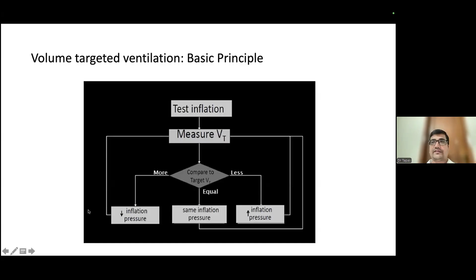Volume targeted ventilation includes many different types. The most common type is volume guarantee, which is present in the majority of ventilators like the Draeger Babylog 8000 Plus and VN500 Accutronic, etc. Then there are pressure regulated volume control, volume assured pressure support, volume support ventilation, and other modes like targeted minute ventilation and proportional assist ventilation, which are mostly used nowadays in adult patients. There are only limited data in newborn use. So don't get bogged down with these terminologies, because they are different names but the principle remains the same.